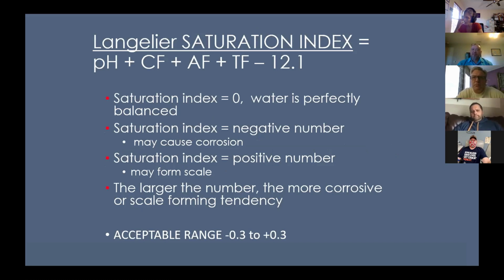When it becomes a negative number, it may cause corrosion. So now you're on the corrosive side of your water balance, which can affect your impellers, any kind of stainless steel fittings that are in contact with the water. Anything metallic that's in contact with water can experience corrosion as a result of improper water balance. If it's a positive number, you may form scale. The larger the number, the more corrosive or more scale forming tendency that water is going to have. Your acceptable range is plus or minus 0.3. That's where I want to be, within that range for balanced water conditions. When you start getting higher than that, then you start seeing that scale formation on the cell.